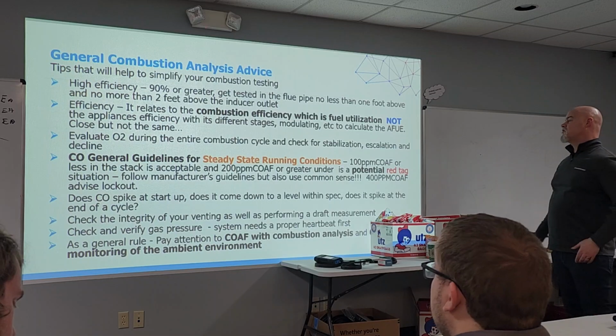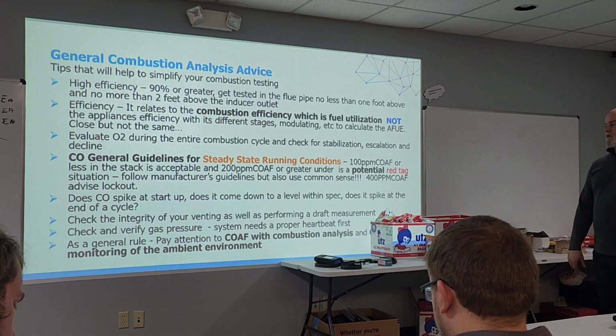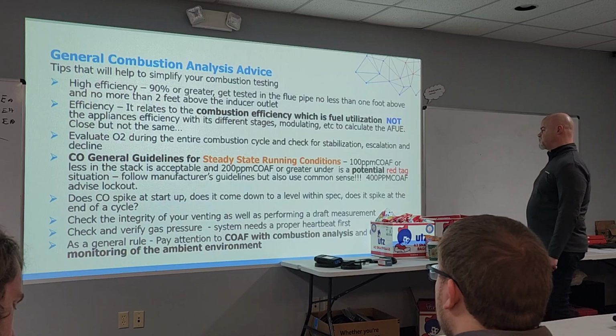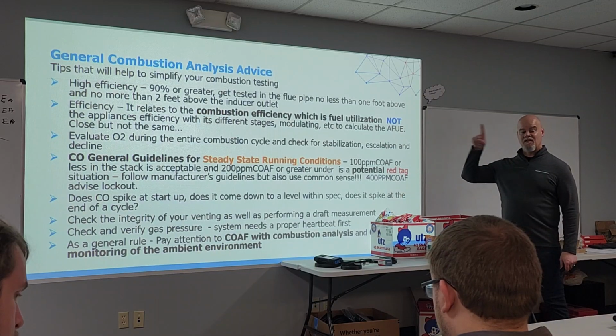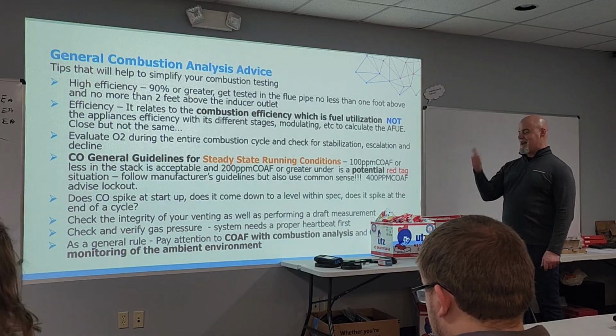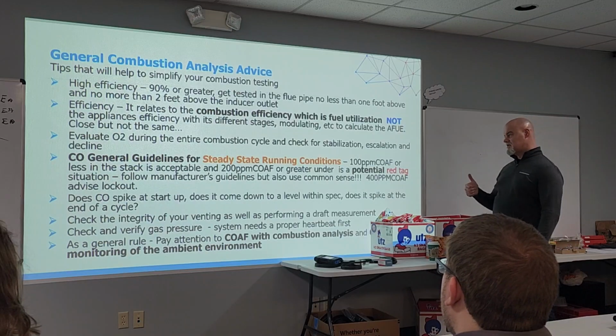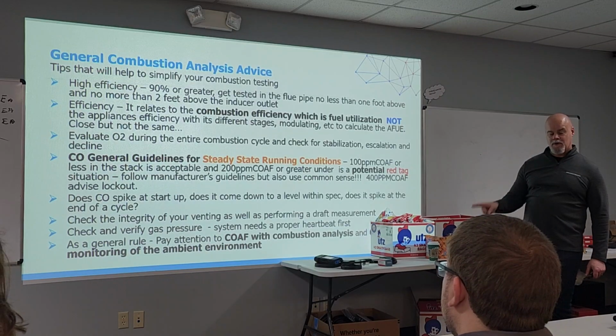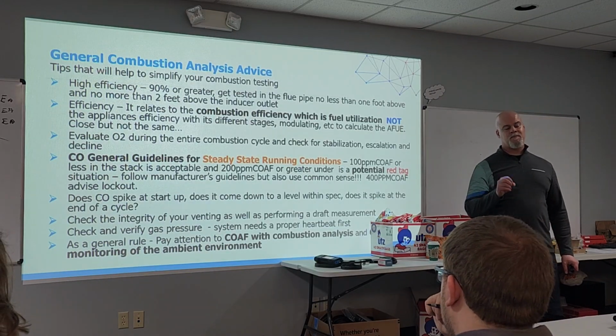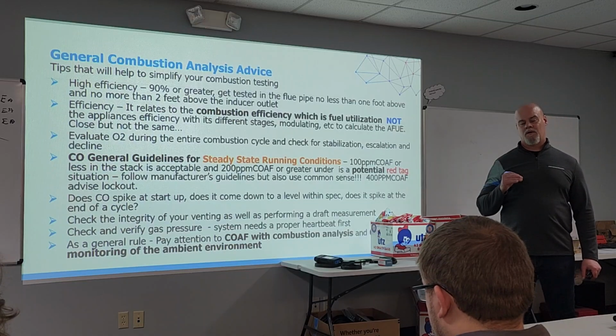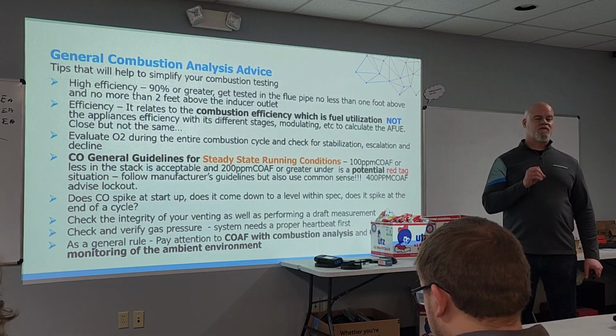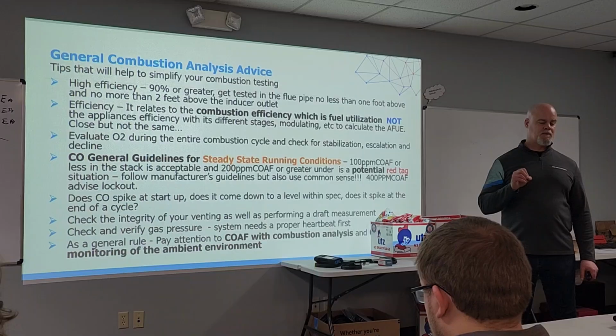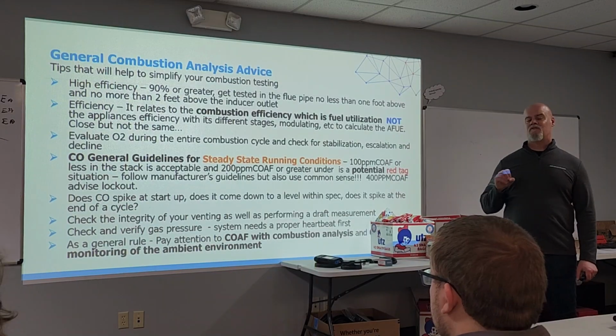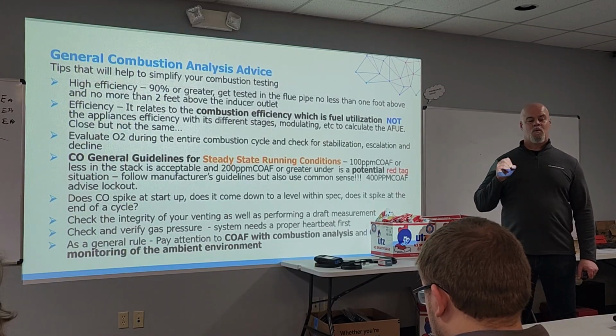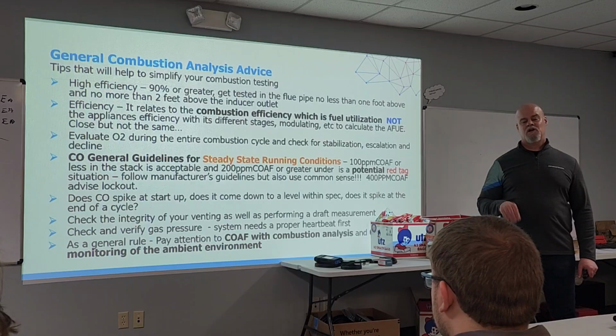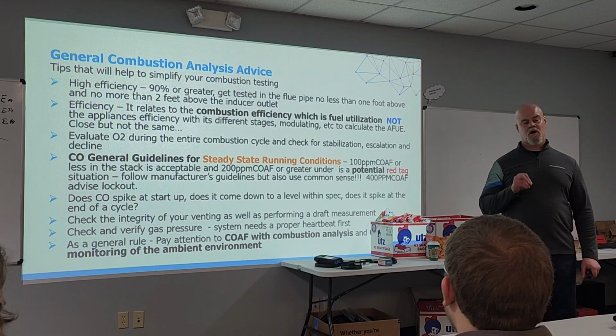Then, here's your first CO guideline I'm going to give you, and I'm going to give you another set in a bit. Steady state only, 5 minutes or greater system runtime. Not light off, not shut down, steady state only. Acceptable in our industry: 100 ppm CO air free or lower is acceptable. We use CO air free instead of CO when we do combustion testing. Why? CO air free is your carbon monoxide number with the oxygen factor extracted out of it. So it is pure, undiluted carbon monoxide.